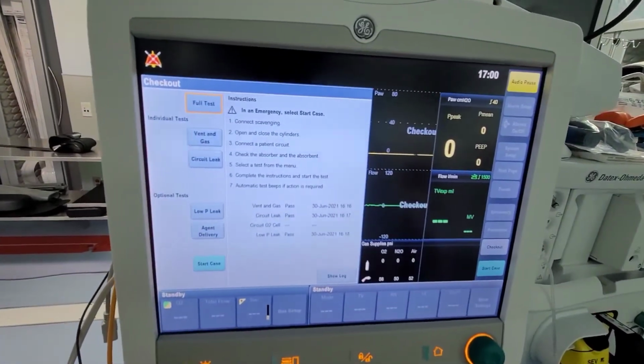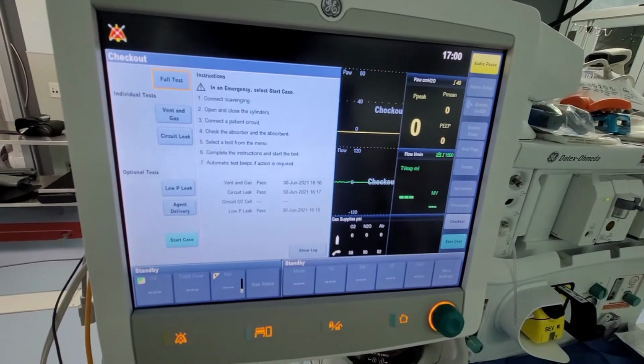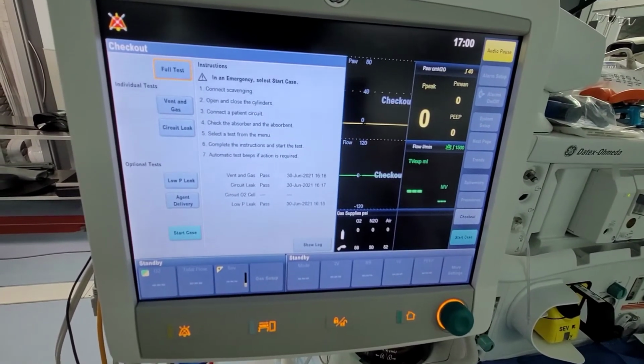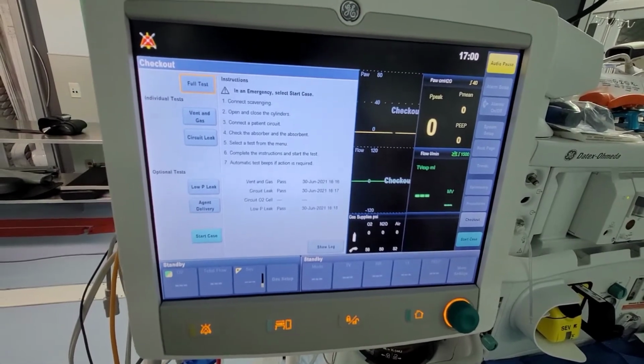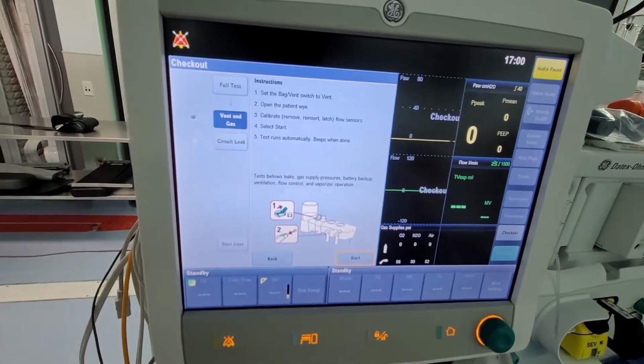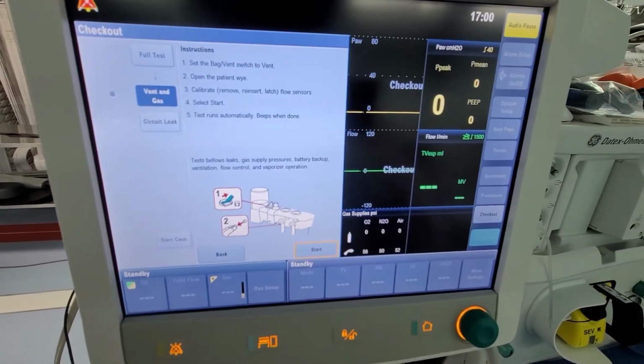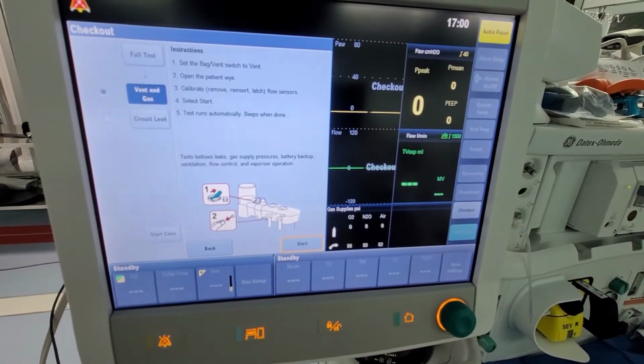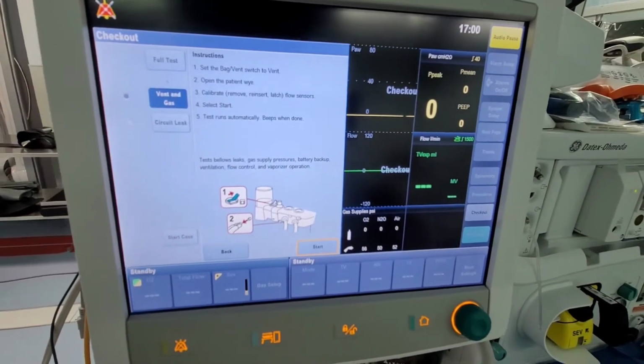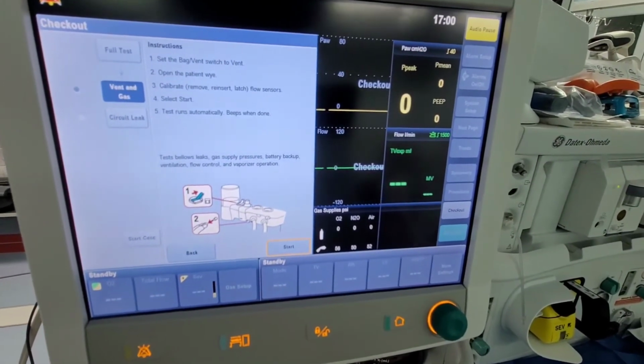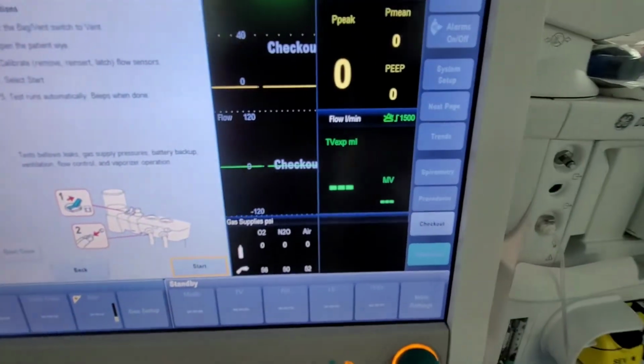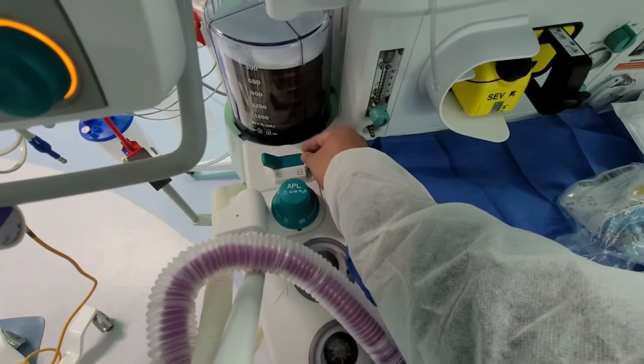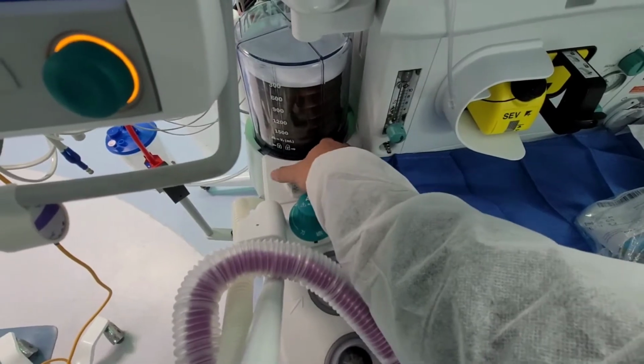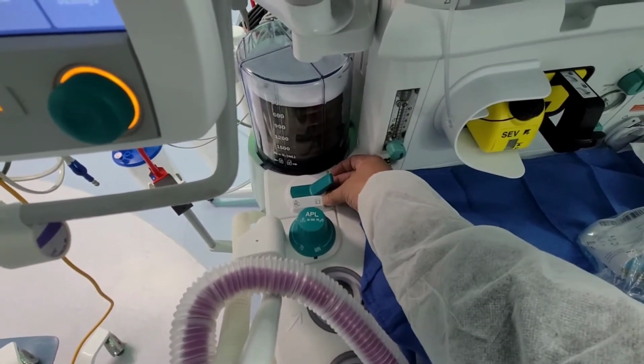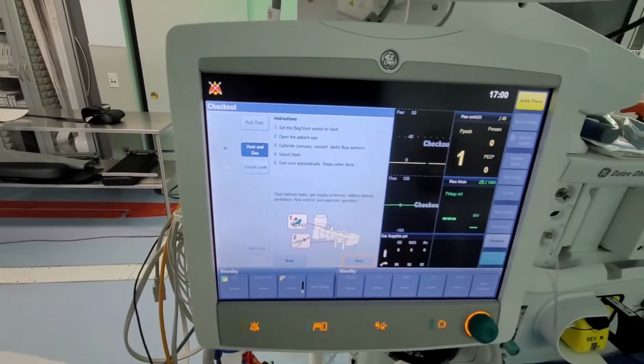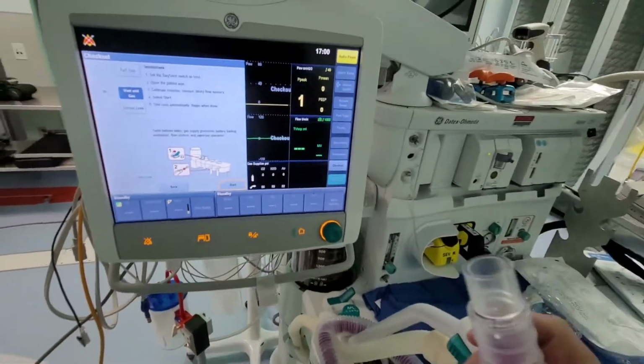Every time you turn on the machine, you'll be presented with the machine checkout. On this particular one, it'll have the full test, so we're going to click on full test. You're going to be prompted with some instructions here. As you can see, the first step is to set the bag vent switch to vent. So over here by the APL valve and the bellows, we're going to switch it over to mechanical ventilation. It says open the patient wye, which it is already.